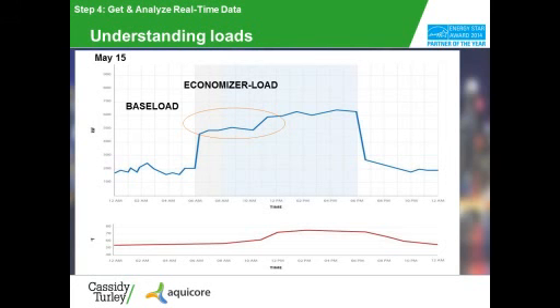The building was equipped with an airside economizer, and it operated without any mechanical cooling. So just fan ventilation. At the same time, electric heat was suspended on the VAVs as well. So now we're operating that building just about as efficiently as we can, and still keeping it maintained in a way where the tenants would be very comfortable. So we're not using mechanical cooling, we're not using electric heat for heating, we're really balancing right in between. And there's a lot of times in the spring and fall that this can be done, probably 60 days' worth. This has been a great June. I mean, we've had some opportunities in June.